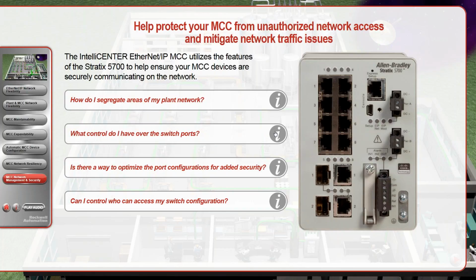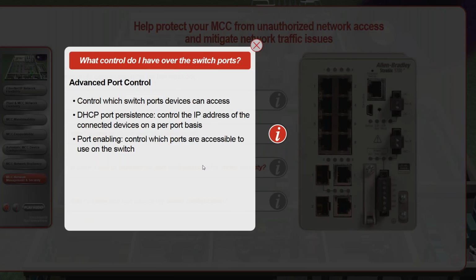So what control do you have over switch ports? We have advanced port control. The Stratix 5700 and our managed switches can understand what's connected to each port. DHCP per port persistence allows an IP address to be assigned to a device connected to that port—you may have heard of BootP-enabled devices, which happens when a device comes straight from the factory, ready to be assigned its identity. DHCP per port lets those BootP-enabled devices assume a particular IP address once connected. Port enabling lets you control which ports are accessible on the switch, in case you want to limit access.